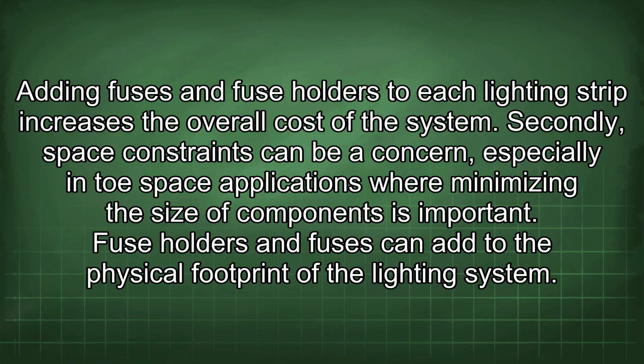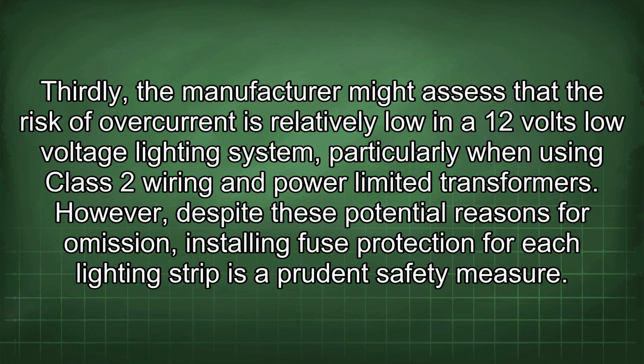Secondly, space constraints can be a concern, especially in toe space applications where minimizing the size of components is important. Fuse holders and fuses can add to the physical footprint of the lighting system. Thirdly, the manufacturer might assess that the risk of overcurrent is relatively low in a 12-volt low-voltage lighting system, particularly when using Class 2 wiring and power-limited transformers. However, despite these potential reasons for omission, installing fuse protection for each lighting strip is a prudent safety measure.